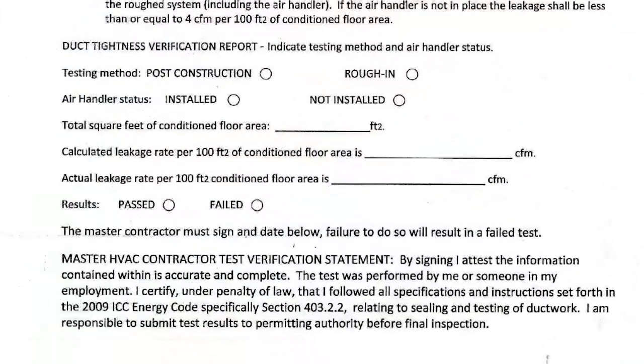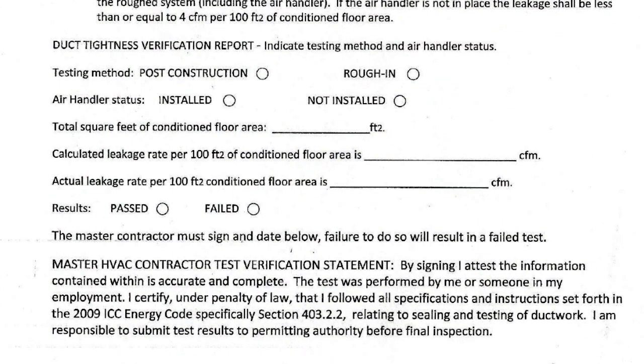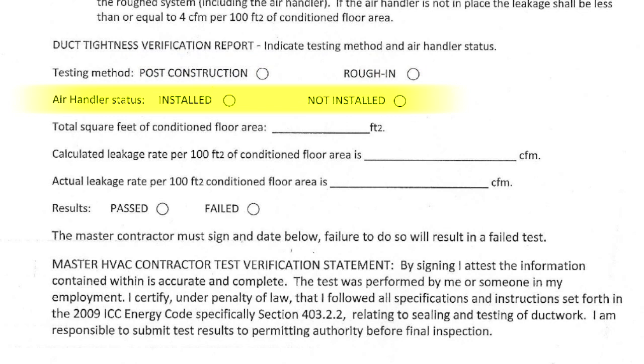So you need to verify whether or not the test was done at the rough-in or at the final, and whether the air handler was actually installed or not. You need to include the square footage for the house, the total conditioned area square footage. So for example, if there is a house with a basement and the basement's not finished, that unfinished basement is also considered in the conditioned area square footage.